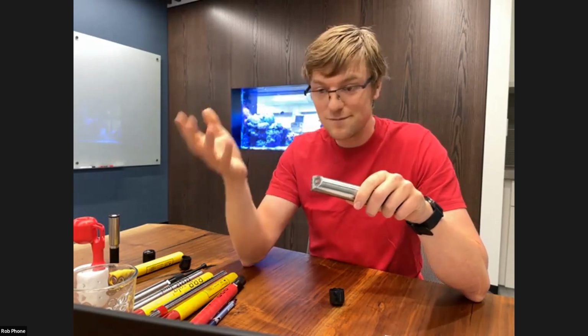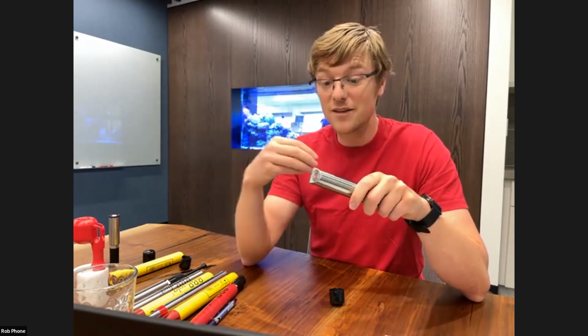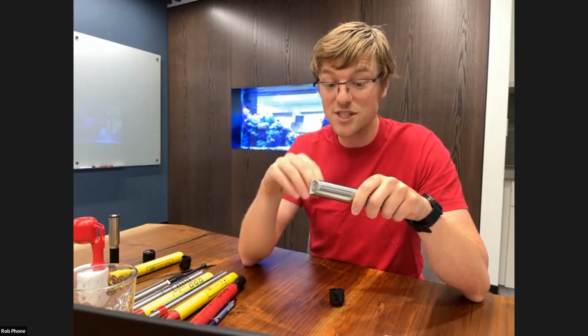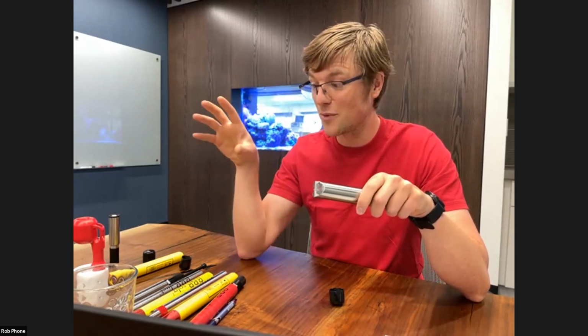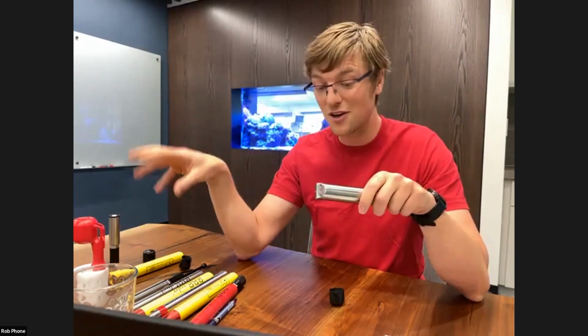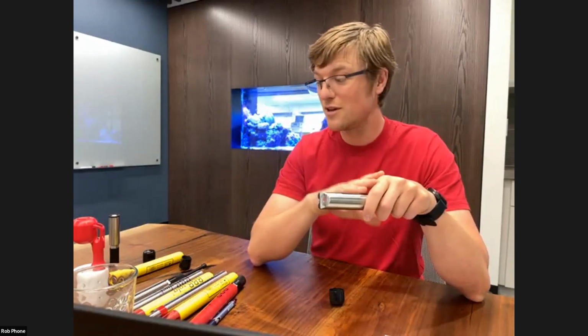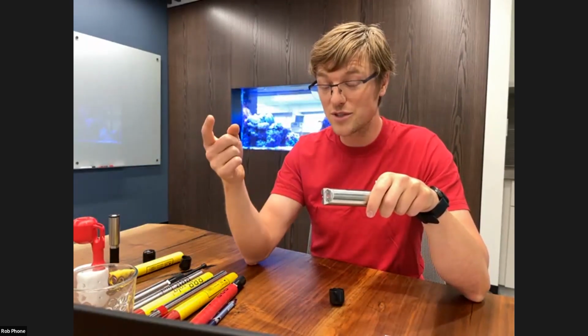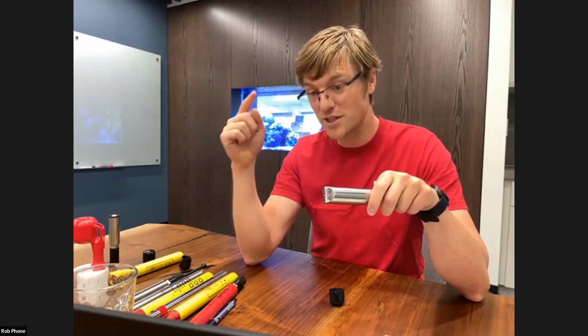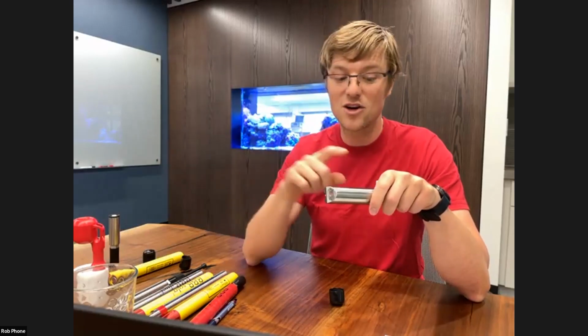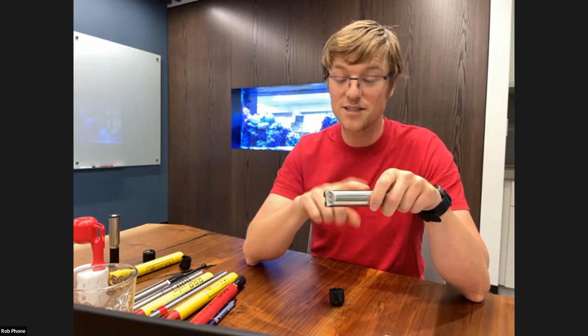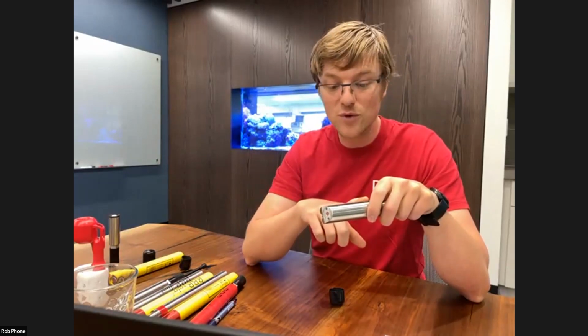So whatever environment you're in, there's a pressure compensation performed on any RBR loggers. So if you have an RBR logger with an optode, the oxygen readout on that unit will take the pressure reading from the logger and compensate your sensor's reading.